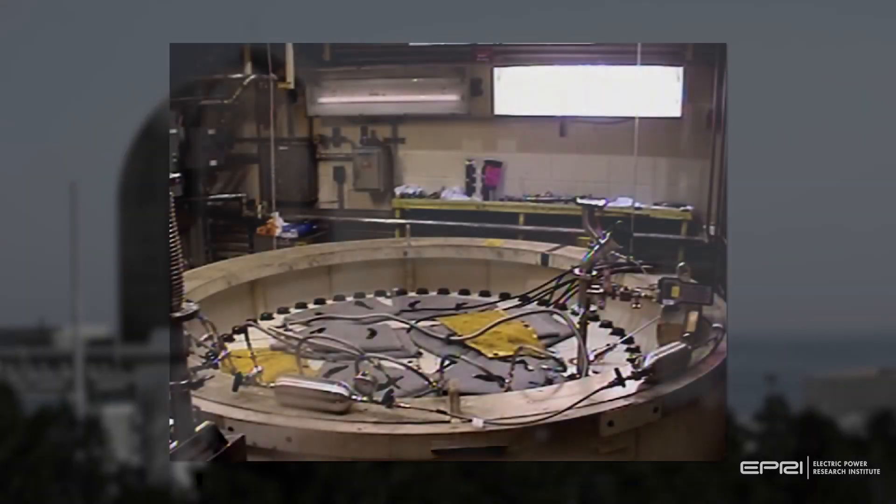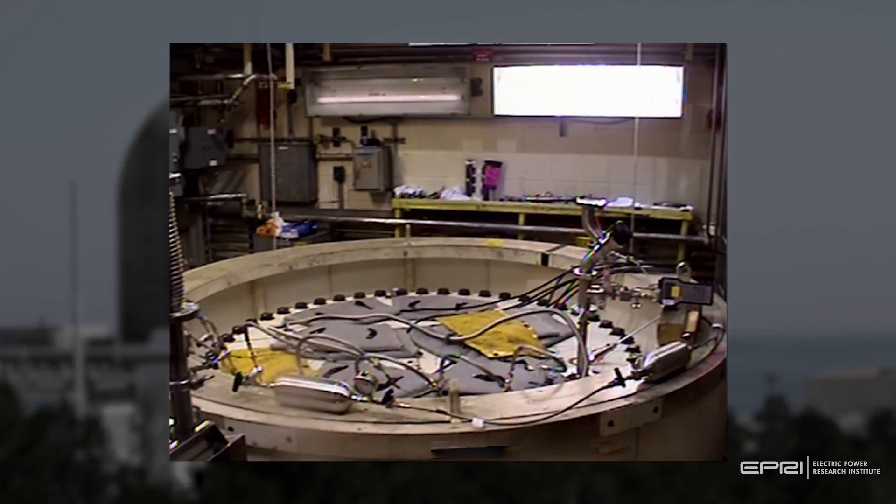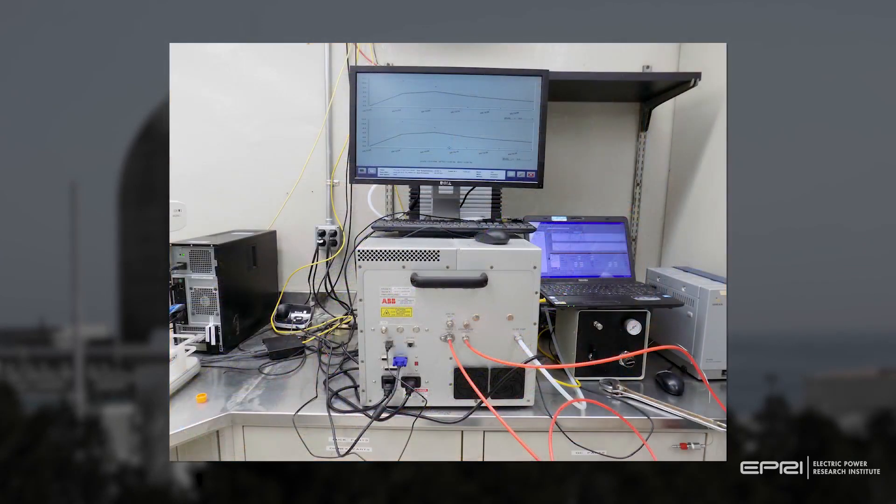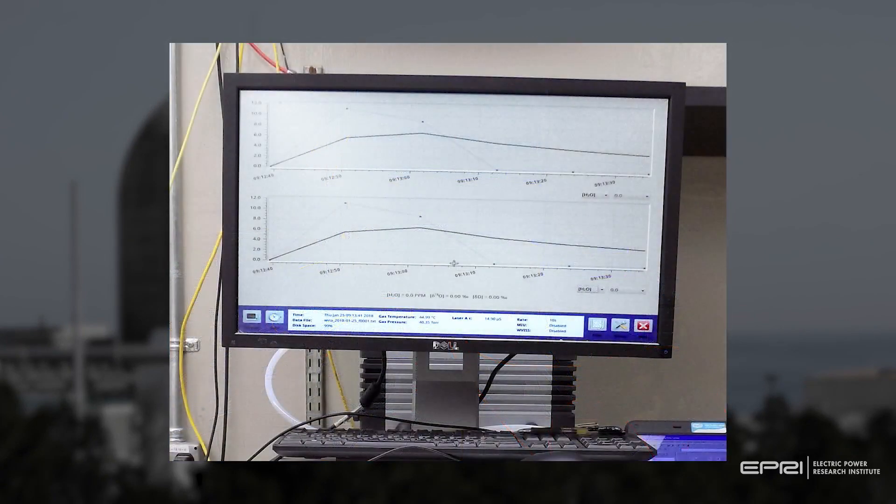The team also collected gas samples from the cask interior at three different times following vacuum drying for laboratory analysis to detect if any fuel rods were breached during the drying process and gain additional information on the effectiveness of the drying process.